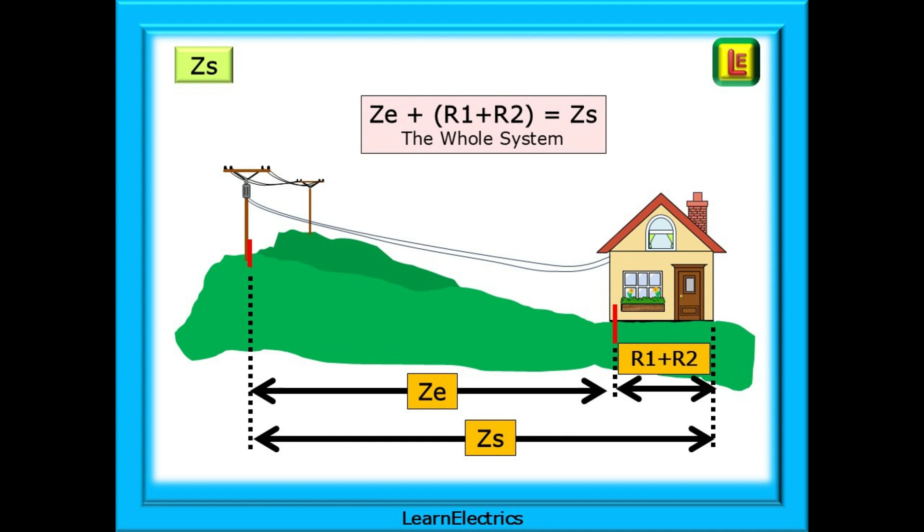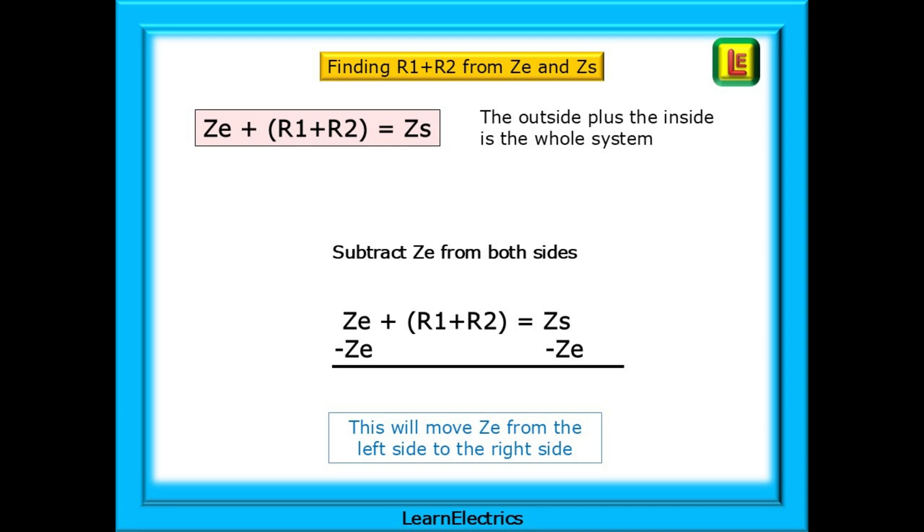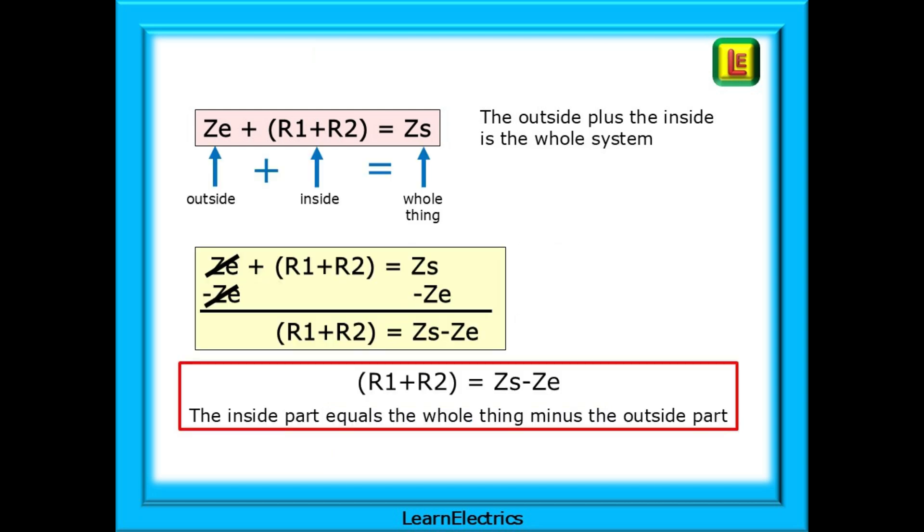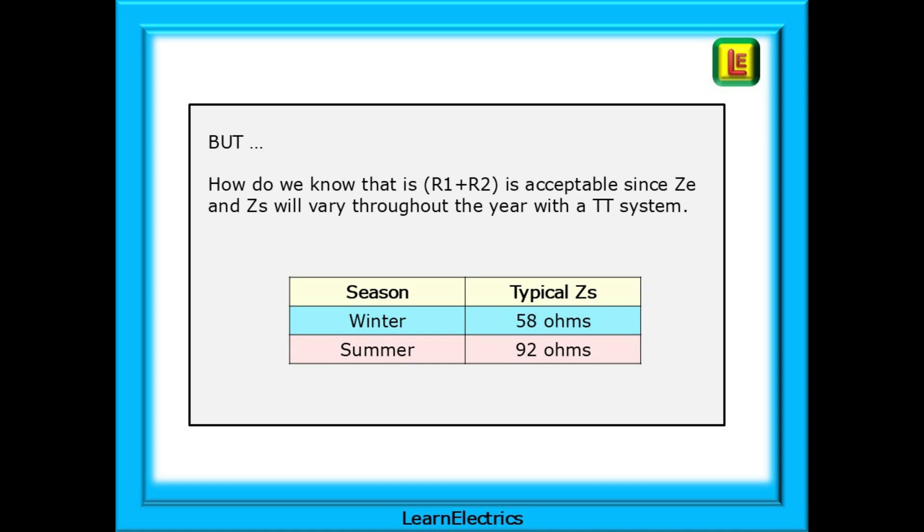ZE is the external part from the house to the supply transformer, and then we have R1 plus R2 for each internal circuit. We can say that ZE added to R1 plus R2 equals ZS, the whole system. How do we find R1 plus R2 from ZE and ZS? The equation shows that ZE plus R1 plus R2 equals ZS. If we subtract ZE from both sides of the equation, this will have the effect of moving ZE from the left side to the right side. And we are left with R1 plus R2 is equal to ZS minus ZE. In other words, the inside part equals the whole thing minus the outside part. But how do we know that R1 plus R2 is acceptable, since ZE and ZS will vary throughout the year with a TT system?